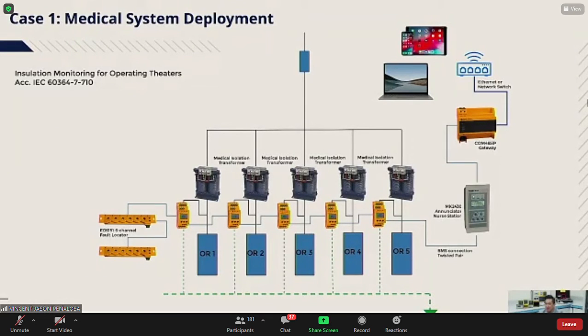So, the budget wasn't as big, but they kind of ran out of it because the installation of the isolated power supply became an afterthought. It was put in, it wasn't part of the original design, up until we informed the owners. And of course each individual room will have its own insulation monitoring device. These things are located on the same floor but in a different room altogether, including the fault locators, right?